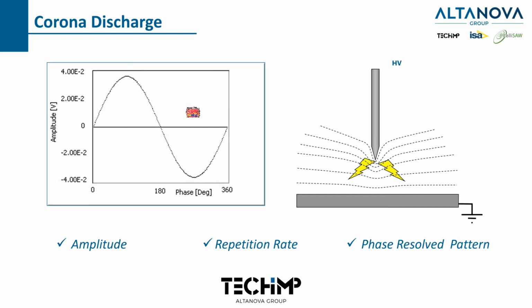All right, so let's just take a look at the three patterns. This is a typical PD pattern for Corona, which is an air gap discharge. And once we know that, we'll take a look at the amplitude and how many times it's happening per cycle, and then we know if it's dangerous to that asset.